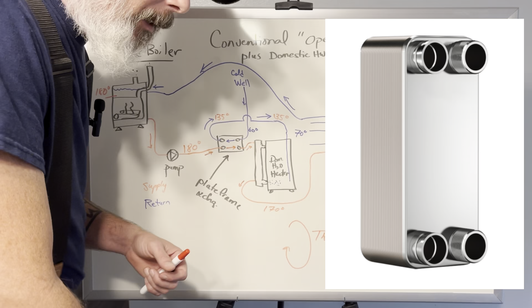Now, plate frame heat exchangers are very high output. You're talking about something that may be half the size of a shoebox that could take 70-degree water and be spitting out 135-degree water. So what size plate frame heat exchanger do you need? Depends on how many showers you want to carry at once, live.